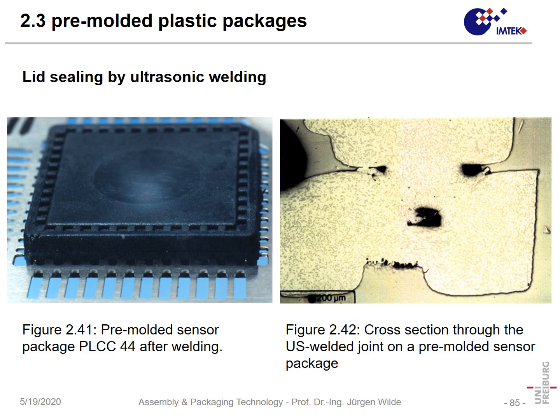Here you can see in these regions we will have a melting of the material. You can have a very proper sealing of the device. It is sealed well, but of course it's not hermetic because it's a plastic material. Also, there is one thing which is important for the material. We have the small gray dots. These dots are glass fibers which are embedded in the material, and they strengthen this material and they lower the CTE of this material.